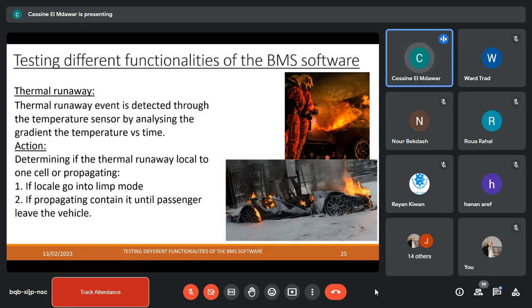Perfect, very well. Usually it's the temperature sensor. If you remember when we started, we spoke about the CSCs — this is gonna be the same temperature sensor that was used there. How we detect thermal runaway is usually the CSCs are tracking the temperature of the cell, and once there's a sudden increase in temperature — thermal runaway happens very fast, the temperature of the battery will go from, let's say, 60, 70 to 200 all of a sudden — if this case happens, the thermal runaway is detected by the BMS.